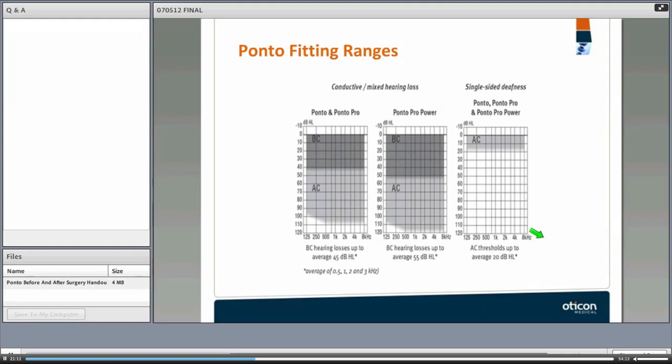In terms of audiological profile, we need to know the fitting range of different devices. We have the Ponto family: the Ponto, Ponto Pro, and Ponto Pro Power. For the Ponto and Ponto Pro, BC thresholds need to be 45 dB or lower. The Ponto Pro Power can fit hearing losses up to 55 dB, compared to 45 dB with the other devices — an additional 10 dB of leeway.